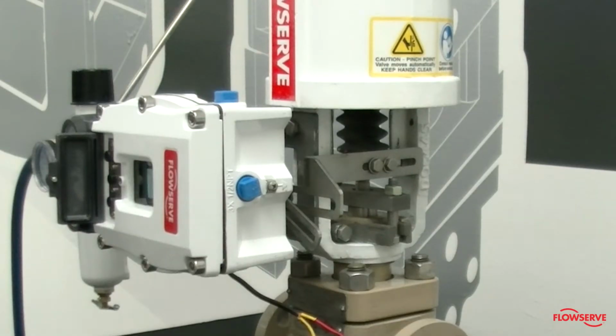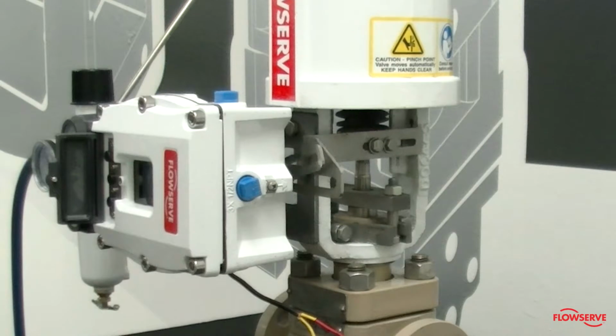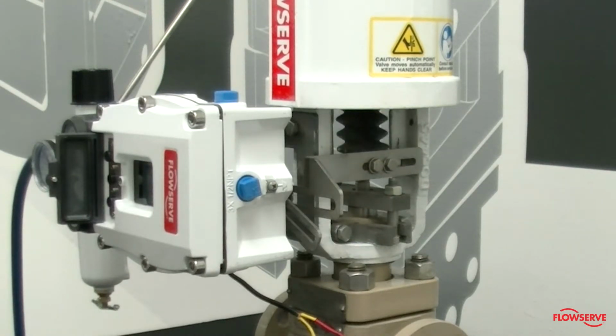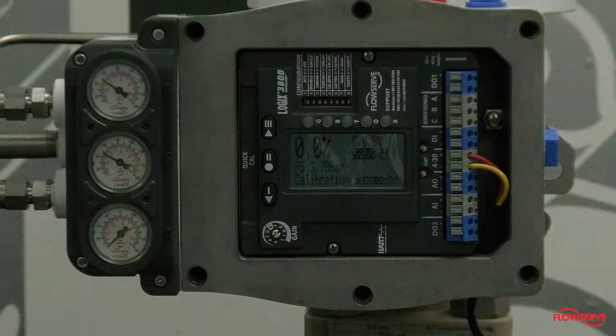Remember that during the calibration, the valve fully strokes twice. Once the calibration is completed, you will see a 4 blink code, and the first blink in the code will be green if the calibration was successful. If the first blink is yellow, then refer to the manual for further instructions.